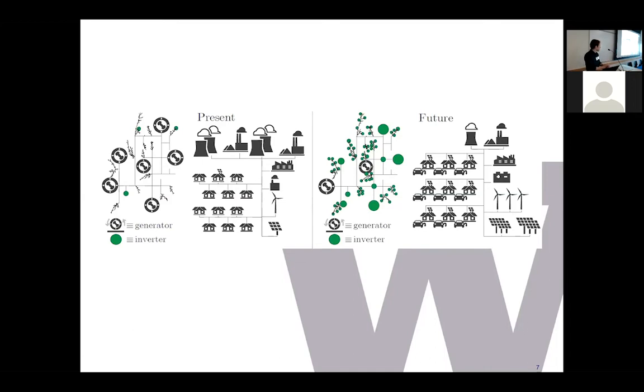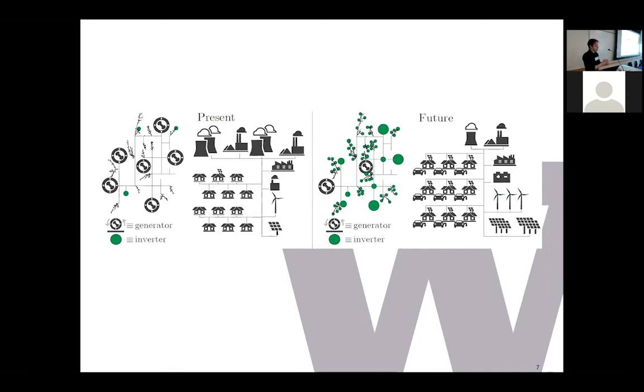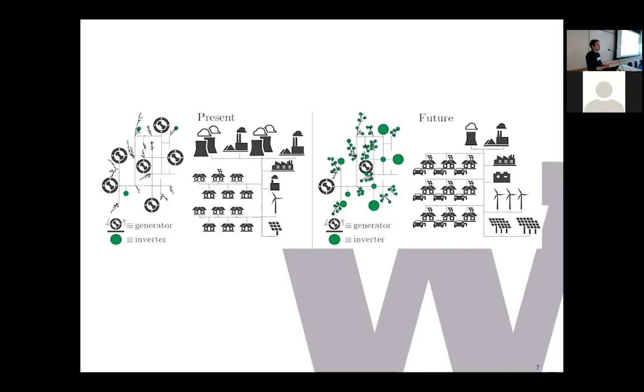The terminology we use to describe that is grid following, and that is the way that all converters connected on the grid today are controlled. But now fast forward and imagine that you're gradually replacing these fossil fuel driven generators with power electronics, things that have no moving parts, it's all just digital controls and electronics. We could be moving towards something where almost the entire grid eventually could be mostly powered by electronics. That's a very different paradigm. Under that paradigm, if you're a power electronic inverter you can't assume that a machine is giving you something nice and stable that you can lock onto. All of the units or at least a subset of the units on the grid have to play an active role in maintaining voltages and frequency across a given system. The umbrella term for describing converters that can regulate voltages and frequency on a system in a decentralized fashion is what we call grid forming.